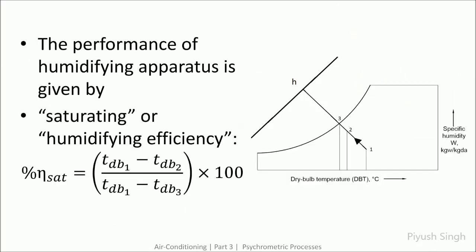The performance of a humidifying apparatus is given by saturating or humidifying efficiency. TdB1 is the temperature of the incoming air, TdB2 is the temperature of the outlet condition, and TdB3 is the temperature at saturation. The total desired drop in temperature was TdB1 minus TdB3, but what could be achieved was TdB1 minus TdB2. Hence, the saturation efficiency is given by the ratio of these quantities multiplied by 100.